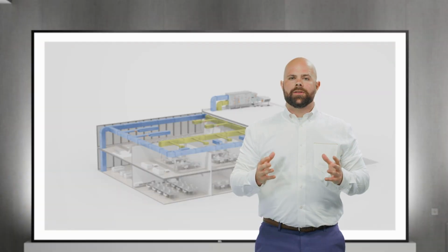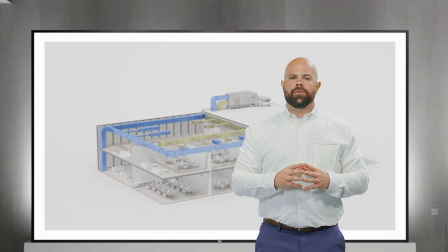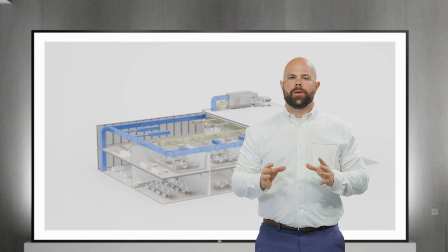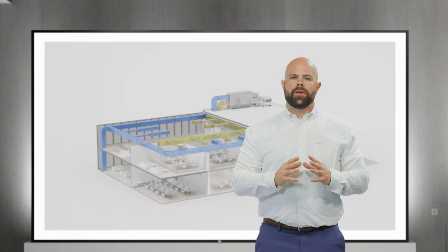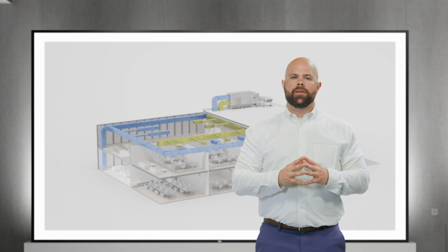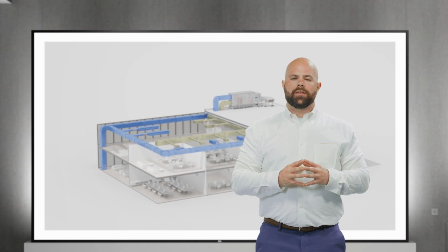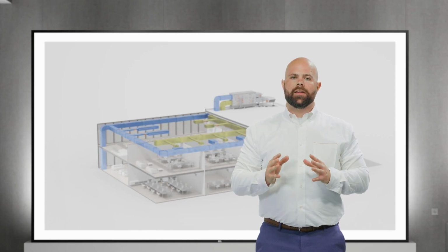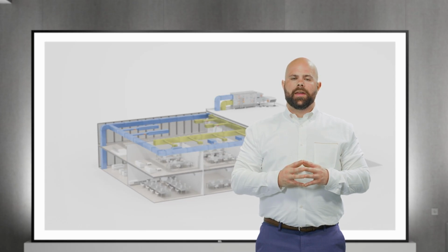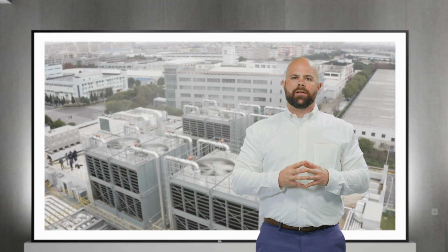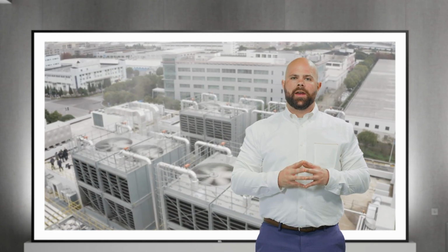In some applications, a central ventilation unit provides fresh, clean air to multiple zones. Each of those zones has its own unique requirements for the amount of fresh air. A way to optimize this is to use a demand control ventilation tactic. In this operation, we provide just the amount of outside air needed to offset the CO2 gases.